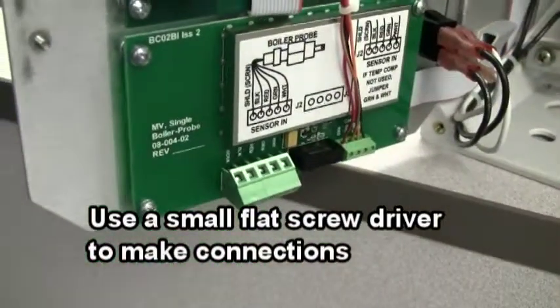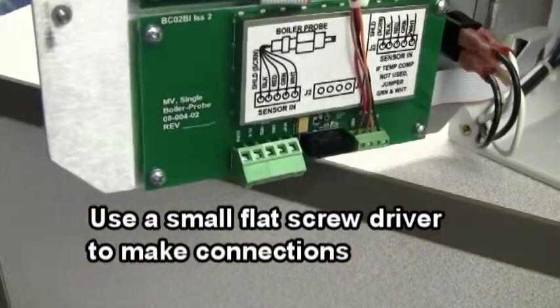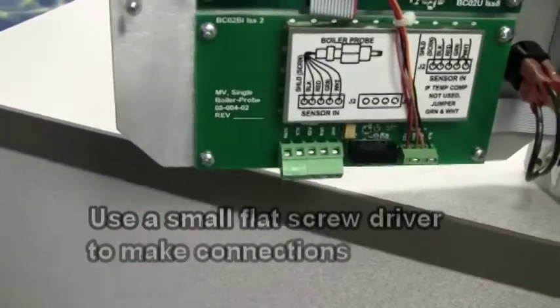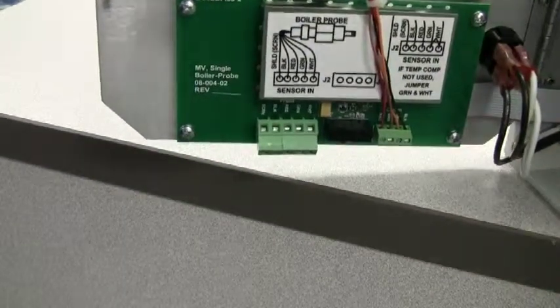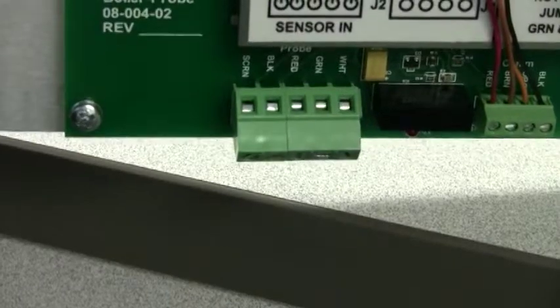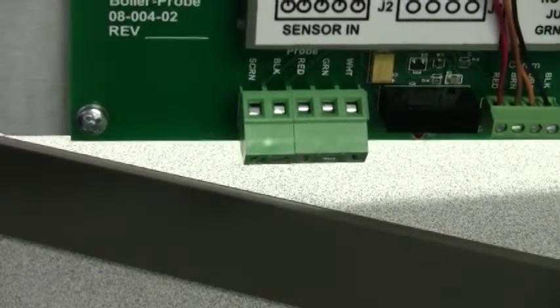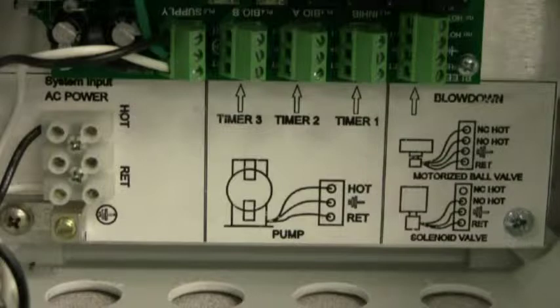In order to wire the sensor, open the front panel of the controller and locate the conductivity daughter card. There's a connector located on the bottom of the circuit board, and there is also a label on the board to help you identify which colored wires go where. Inside the controller, the incoming AC power and all of the output terminal locations are clearly identified by a label.